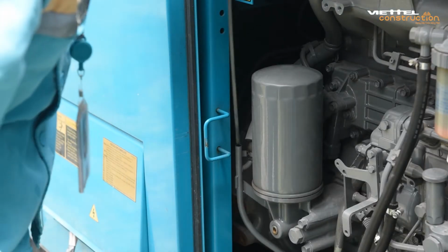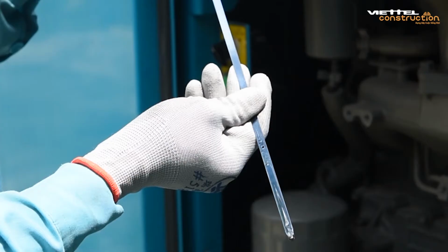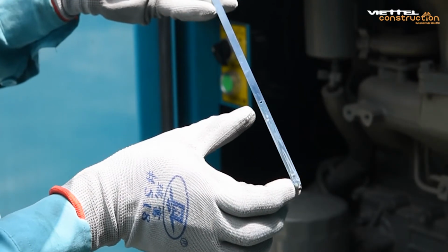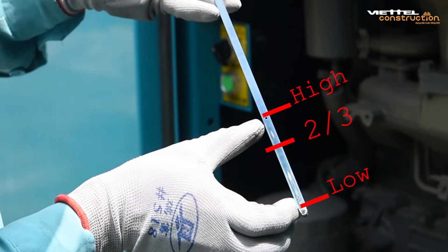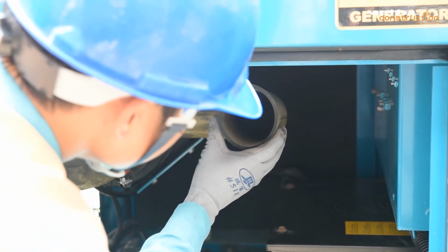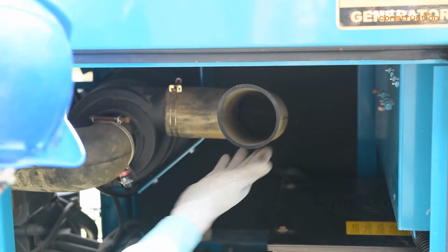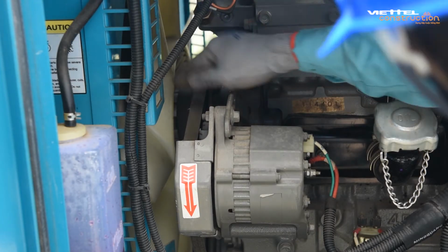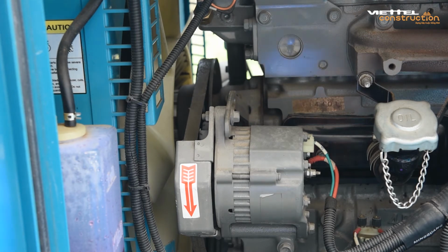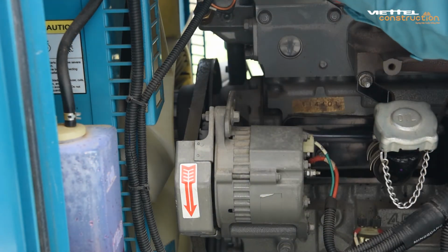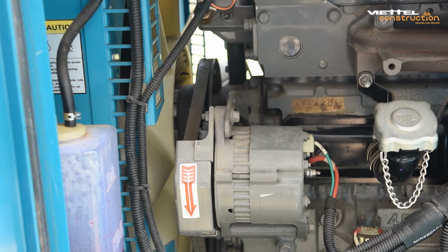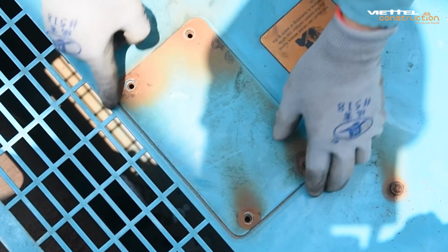Check engine lubrication, make sure the amount of lubricating oil is always at about 2/3 between the lower limit line and the upper limit line on the dipstick. Check the air filter system to make sure the air filter has no obstructions on it, along with the cooling system. Then check the cooling fan blades by hand in the airflow slot on the body of the machine. Make sure the fan blades are not stuck or loose with the shaft. Check the deflection of the belt, then check the coolant level.